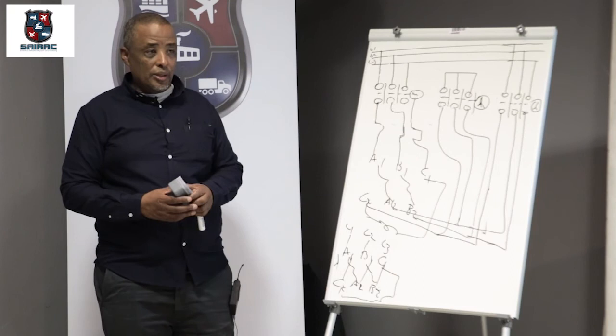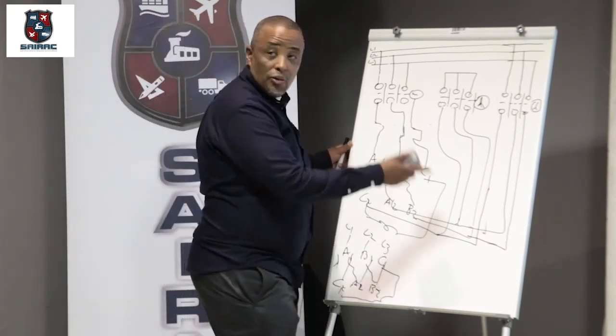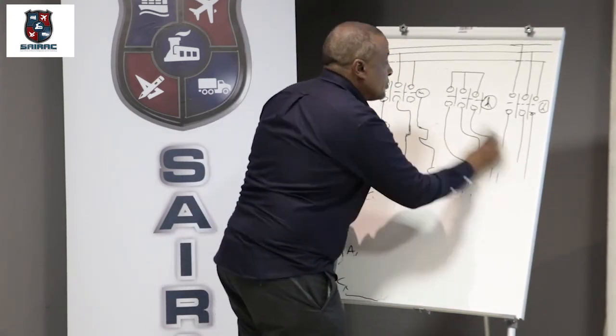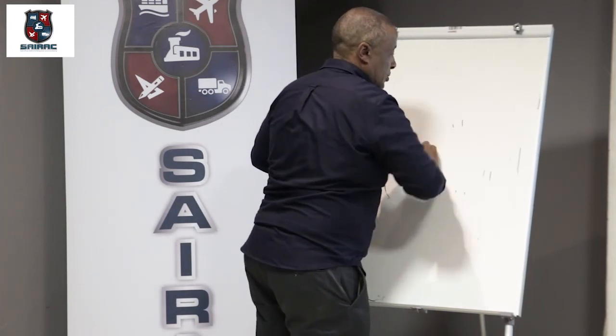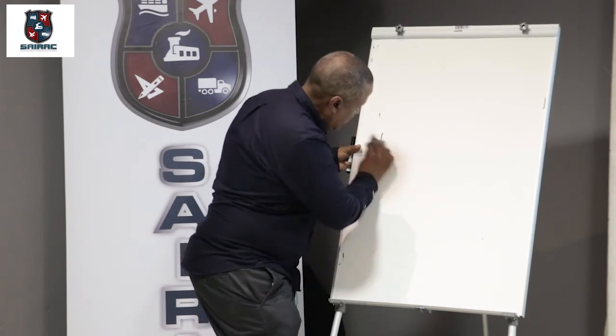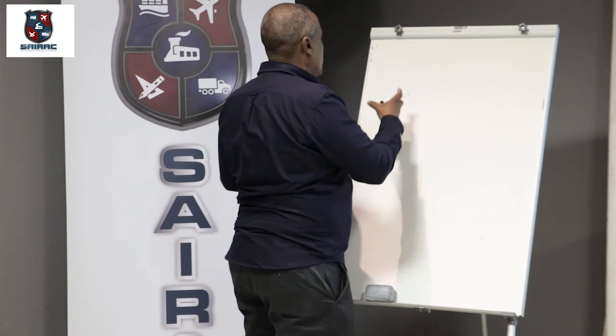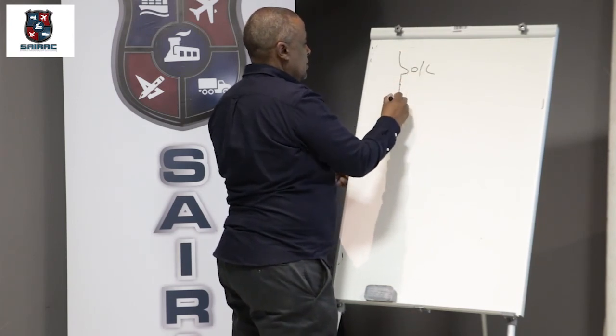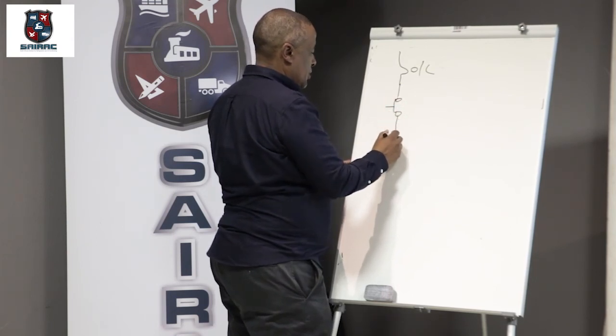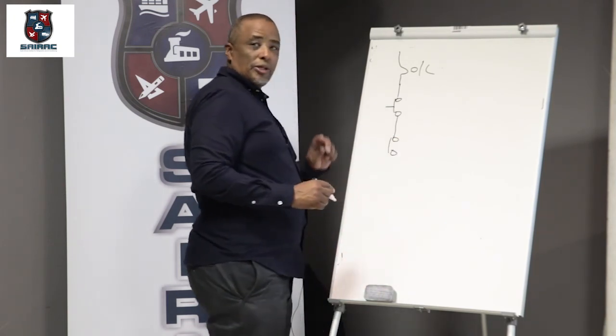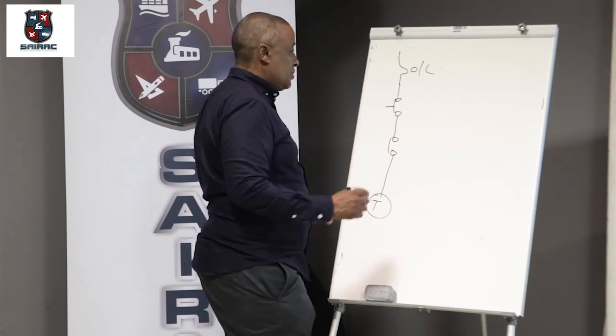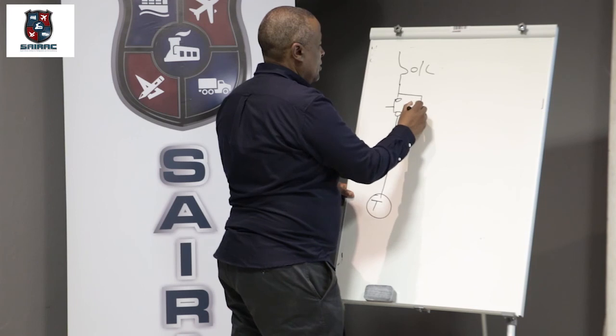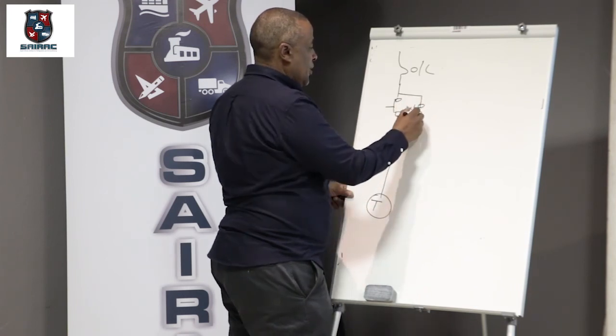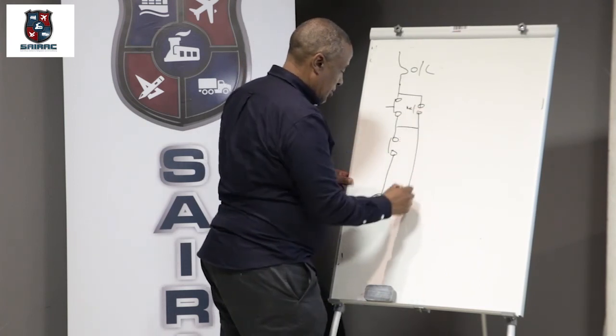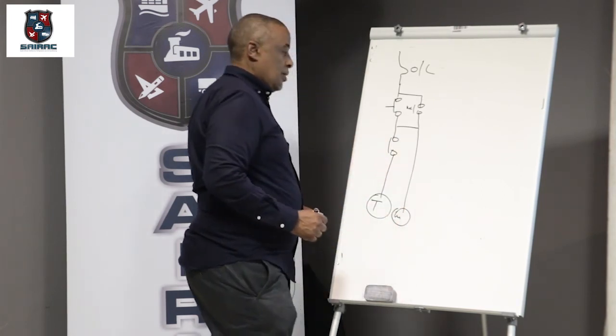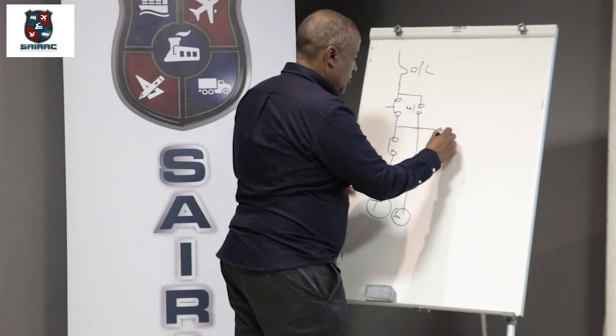Okay, this control circuit. Can I draw the control circuit quickly? Okay, you all happy with that? We know what must happen. On the control circuit, we can have the overload there. We can have the stop button. Start. Okay, when you press the start button, the timer coil must energize. What else must be energized? The main contactor. It's auxiliary from the main contact. The main contactor must also come in, as well as the star contactor as well.